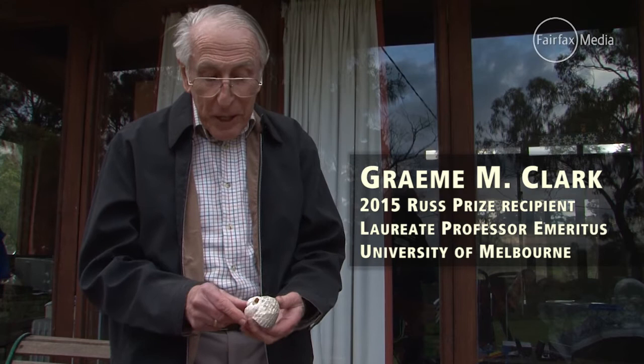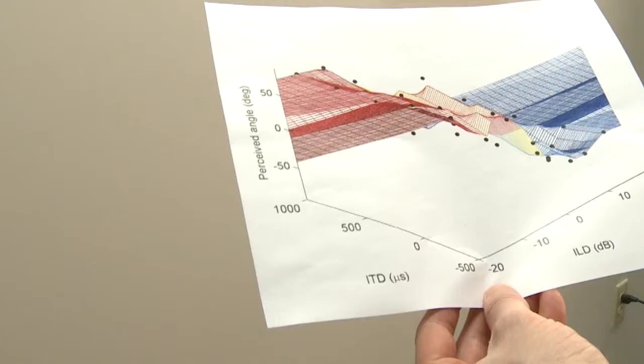The challenge was to put a wire around that, and I got the idea from a shell and found that the wire would go in if it was bent and flexible. That then led us to designing the first prototype. Our contribution was the design of a multi-channel micro-electronic cochlear implant, which is the prototype of presently available implants. We also designed the electrode which is inserted into the scala tympani. The electrode arrays had been developed before we came along, principally by the other winners of the Russ Prize, and we discovered new ways to utilize those electrodes more effectively, such that most persons using cochlear implants could understand conversational speech with hearing alone and without the aid of lip reading or other visual aids.